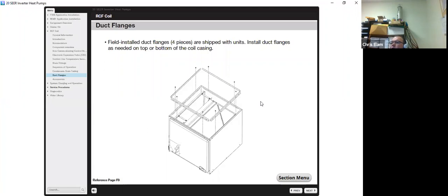Once you receive your coil, in the box you will receive field installed duct flanges if necessary. The 4 pieces are shipped with the units. Install the duct flanges as needed on top or bottom of the coil casing. See right here, and all your holes are already pre-punched for it.